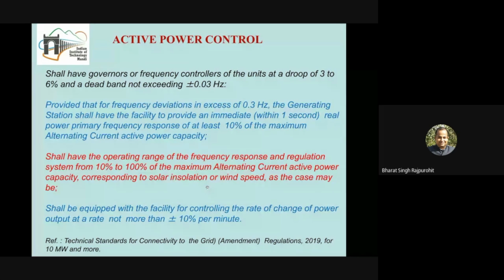So now you will be able to see that whenever the frequency deviation is in excess of 0.3 Hertz, the generating station, which should not be only conventional but also with solar panels, SPV farms or wind farms, should be able to provide the frequency response of 10% of the maximum AC power. So this is what is expected. When the deviation is beyond 0.3 Hertz and the frequency is increasing, it is possible to reduce the output from a wind turbine. The output should be reduced by 10% for every 0.3 Hertz.